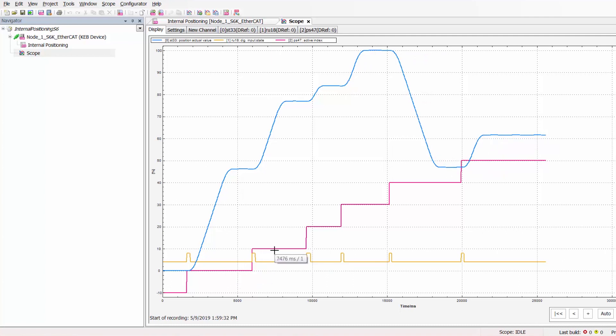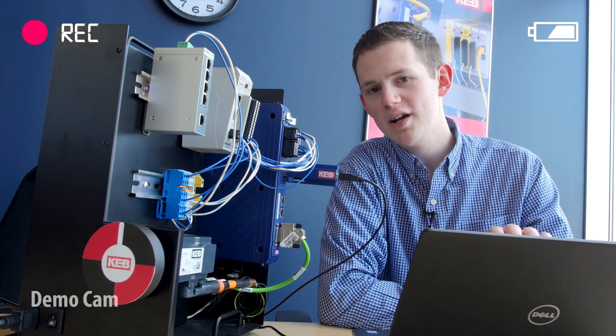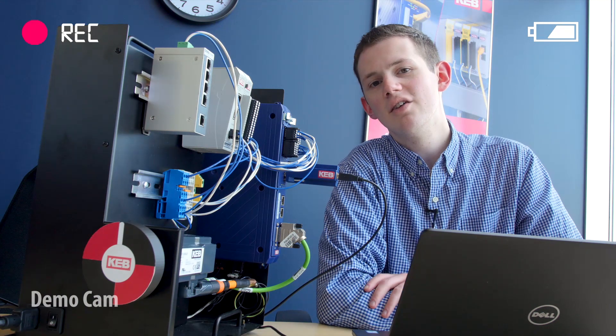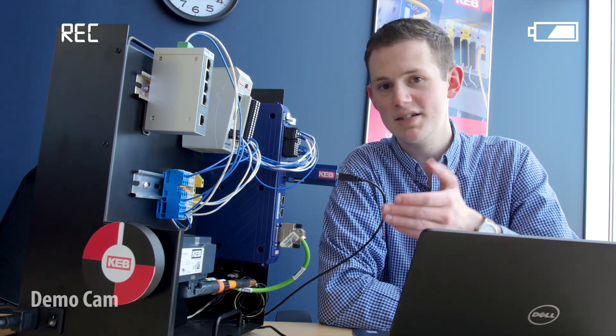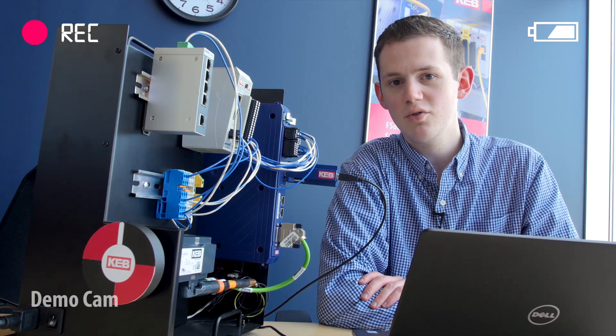Now that we have reached index 5 we are going to go ahead and stop our scope and this is the recorded data that we have obtained from the positioning. This blue line or curve that we see here represents the positions that were obtained from our indices. The magenta steps are the different index positions and the active index that was obtained and these orange pulses represent the positioning commands that were given inside the drive. And just remember from the program we created we set the target velocity to be 0 RPM so when the positioning is completed as it is now the drive will hold at zero speed awaiting a new command.